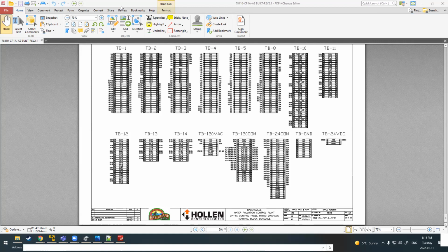Alright. So redundancy for automation systems is kind of system integrity. Let's say you have a 24-volt power supply, and if that power supply fails, you don't have any more 24-volt in your panel. If you have a redundant power supply, you would have two power supplies in your panel, and a third device that would switch between them, so that if power supply 1 failed, power supply 2 would keep powering your 24-volt circuit. Okay, so it's just available just in case. Yeah, duplicate.